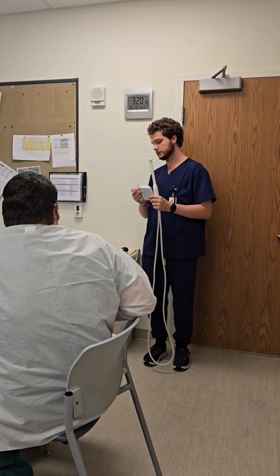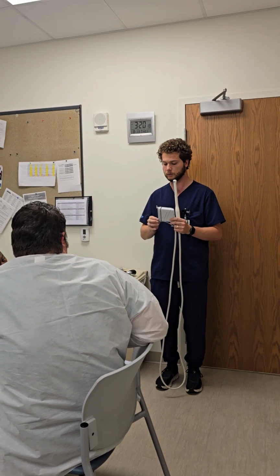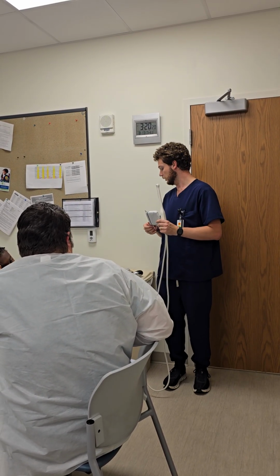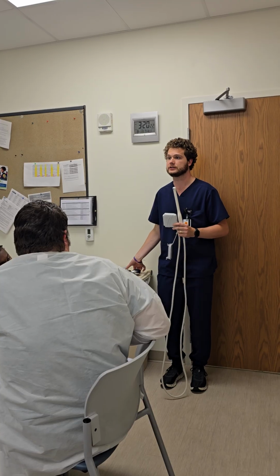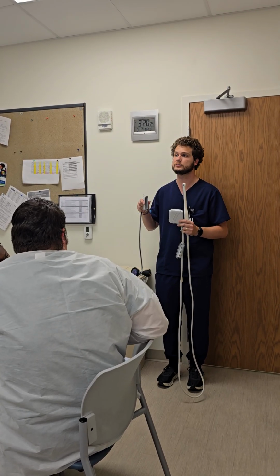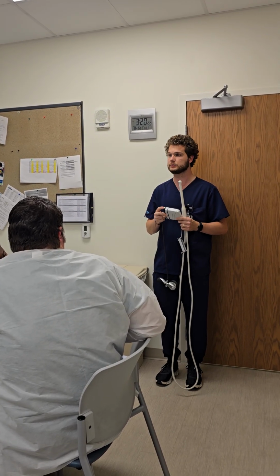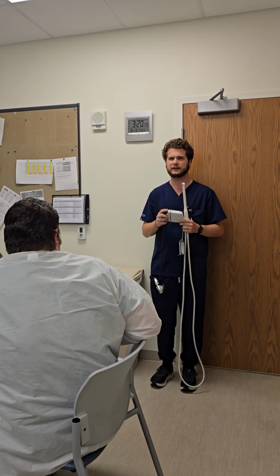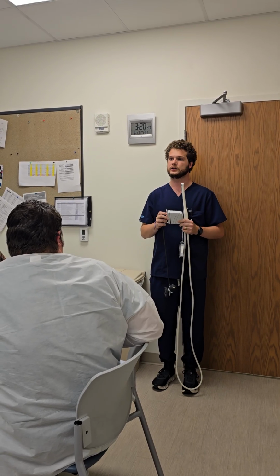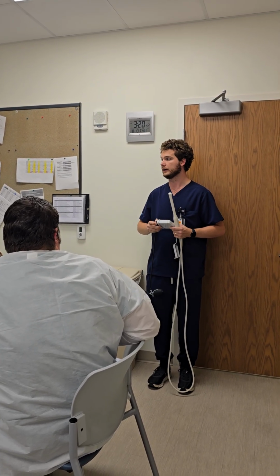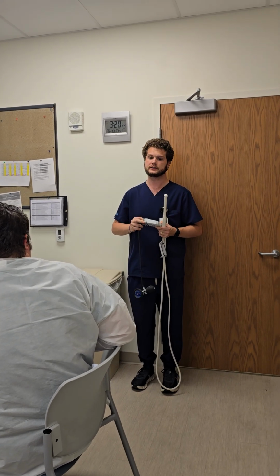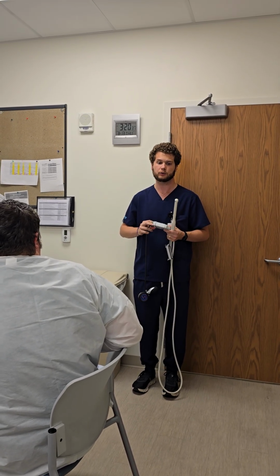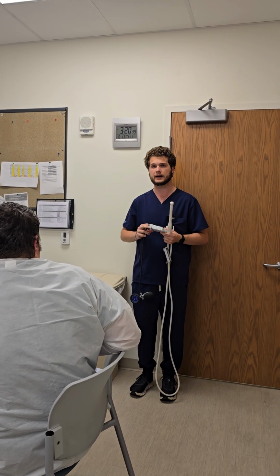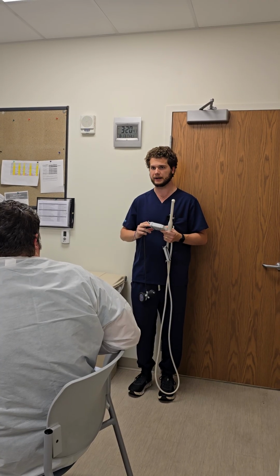Now for the pressure test, we do 2 steps. Like I said, the dry and the wet. We are going to blow up the pressure to 150, plus or minus 5. If you blow it up to 160, it's going to lose pressure faster and it's going to look like a fail. It's not a fail. Just get it as close to 150 as you can and then start watching. For the dry test, we are going to watch for about 45 seconds. It can lose up to 10 psi. Up to 10, still a pass.